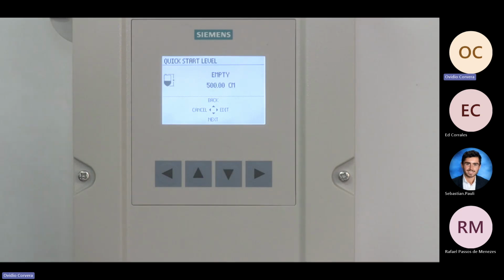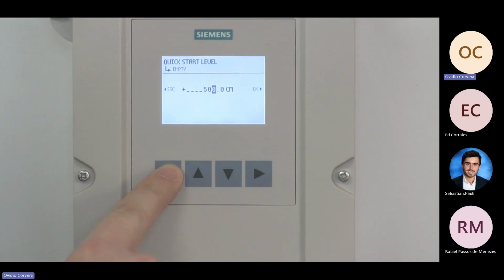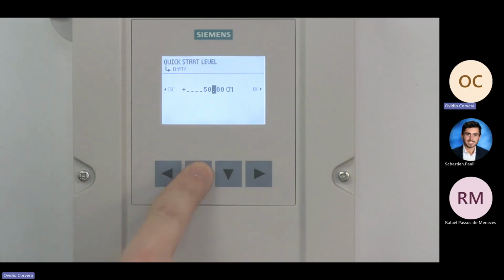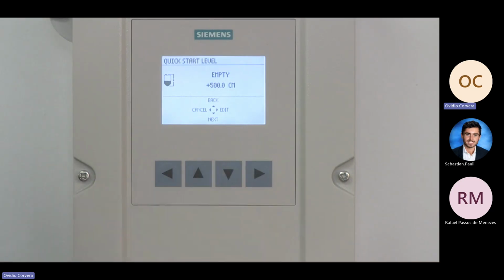The next step in the wizard is to enter the empty distance. The empty distance is the distance from the face of the transducer to the process empty point. Press the right arrow to select Edit to modify the empty distance value. Use the left and right arrows to move the cursor and the up and down arrows to modify the empty distance value. To move the decimal point, position the cursor over the decimal point and then use the up arrow to move it to the left and the down arrow to move it to the right. Once you have put in your empty distance, press the right arrow to highlight OK. Press the right again to accept the empty distance. Press the down arrow to select Next to proceed.